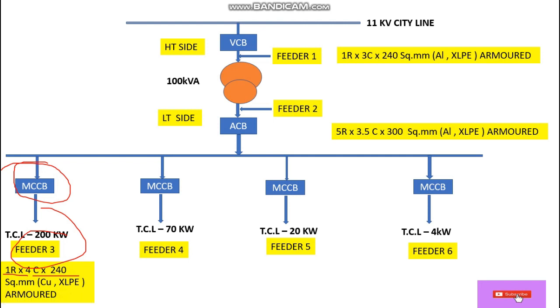In this way we can calculate the LT cable size considering the derating factor. For Feeder 3, the cable size is one run of 4-core 240 square mm copper XLPE armored cable. Hope you guys understand. Thank you for watching — please like, share, comment, and subscribe, and hit the bell icon for notifications. Thank you very much, see you in the next video.